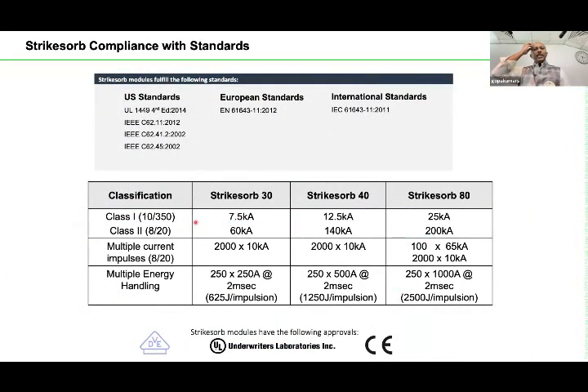Now, the advantage of these SPDs, as I said, is that there are 3 models, Strikesorb 30, 40, 80. And these SPDs we can call type 1+2, because both the 8x20 and 10x350 waveforms are tested, for example 7.5 and 60 kiloampere, 12.5 and 140 kiloampere, 25 and 200 kiloampere. Similarly, for multiple current impulses, all these SPDs are tested for 2000 strikes of 10 kiloampere. 2000 strikes of 10 kiloampere. We should also understand one important subject. Lightning sometimes is a continuous phenomenon. One after the other, it will fall.